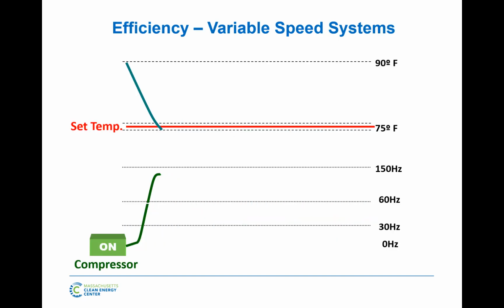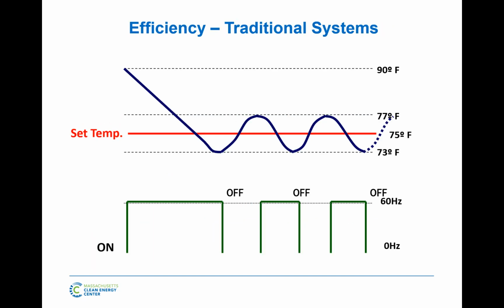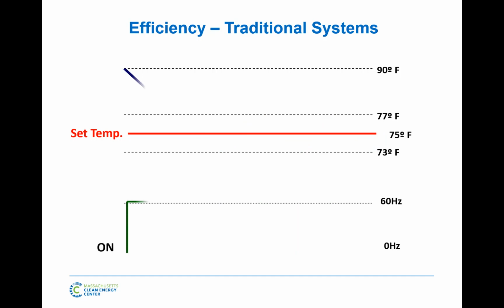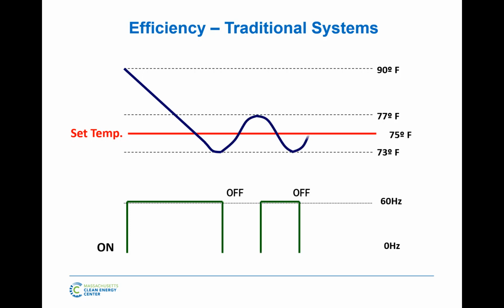I'll go back to what I was going to show here, which is part of the efficiency, and this talks about comfort a lot, but it does affect efficiency. It is the difference between an air source heat pump and a regular water source heat pump, or a PTAC in a hotel. The way those work with regular thermostats is, hey, I'm on, I want cooling, so your compressor turns on, you get cooling. Then your thermostat says, oh, I'm satisfied, turn off, so the compressor turns off, the room temperature rises up. And it hits 77 again, turn back on, off. So these become on-off systems.